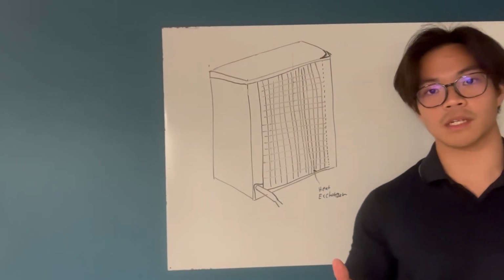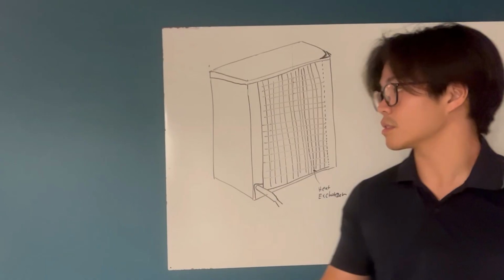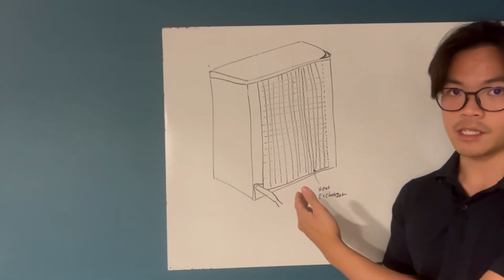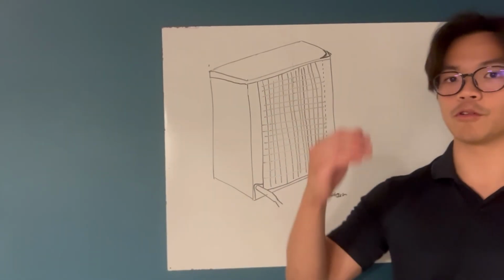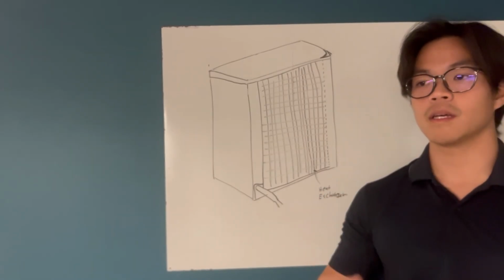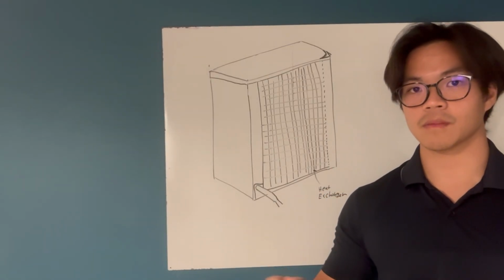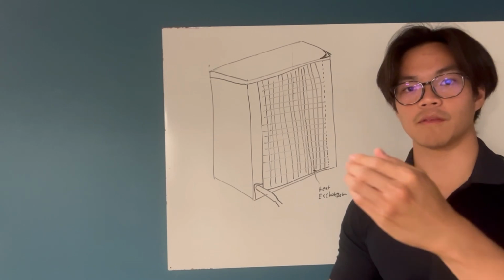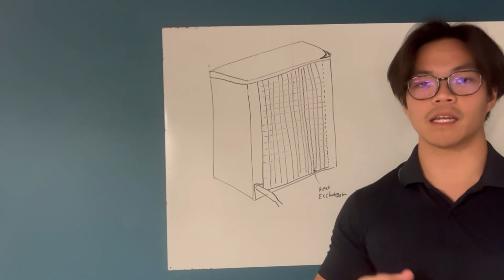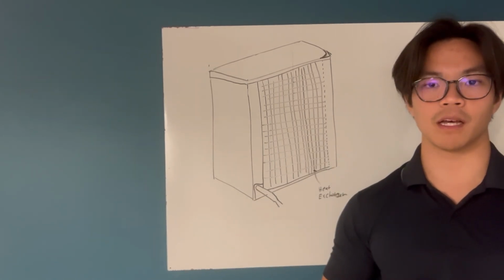In order to do the smoke test, firstly we need to block the heat exchangers. This shaded area of this heat pump is the heat exchangers, and we will be blocking them with saran wrap. By completely blocking the heat exchangers, we will stop air from flowing through them, which will highlight any bypass sites the heat pump will have.